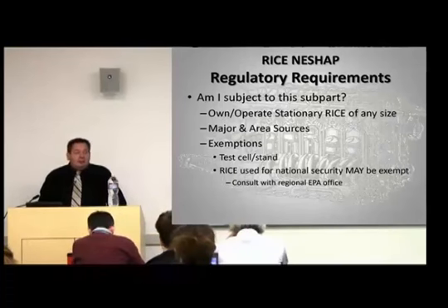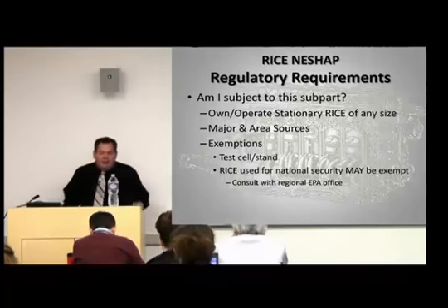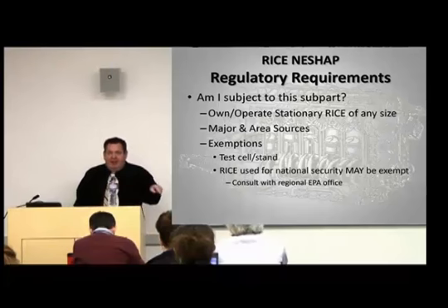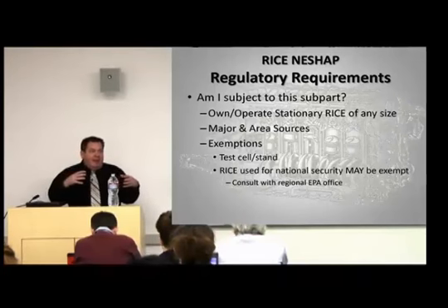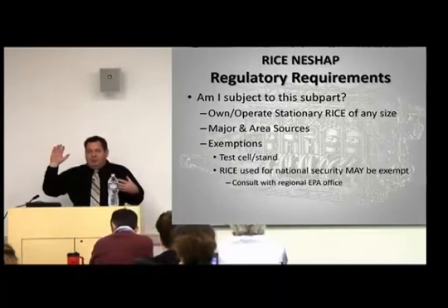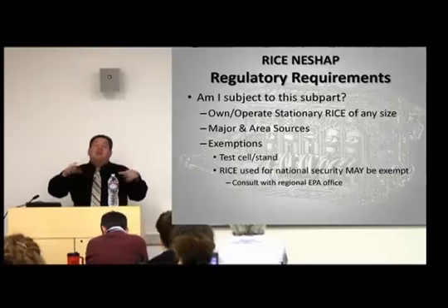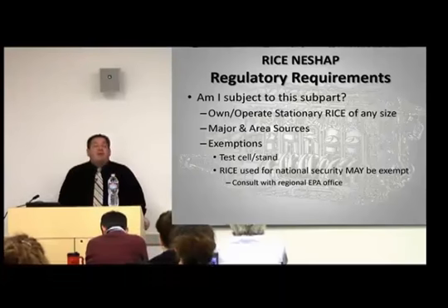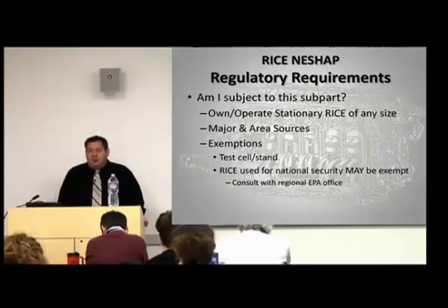Are there any exemptions? Yeah. One is an engine operated on a test cell or stand. This is under the general provisions, and it is specifically for engine manufacturers. The theory is that engine manufacturers operate engines before they send them off to their distribution center. So if they're testing their engines before they ship them off, those engines are exempt from the regulation. All other engines operated on test cells or test stands are subject to the regulation.